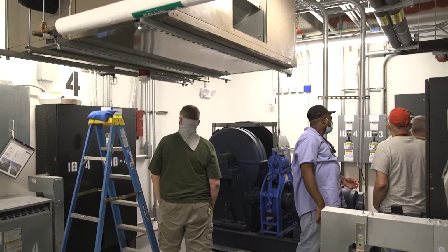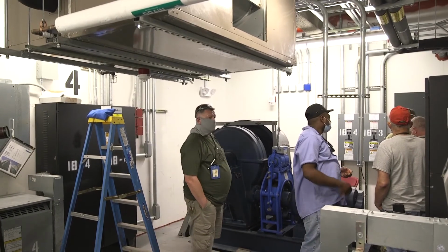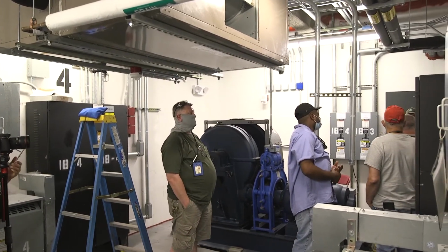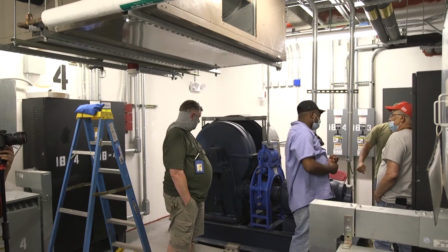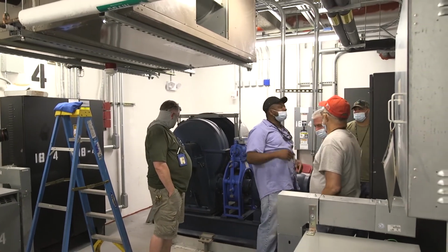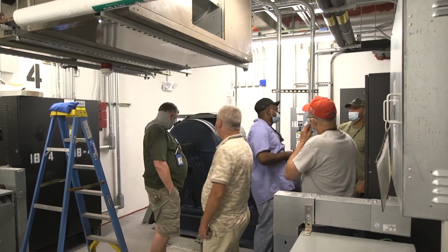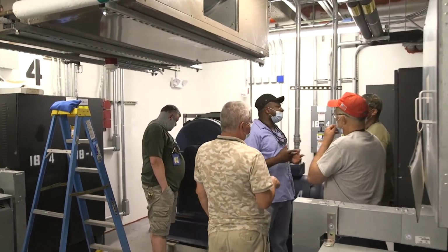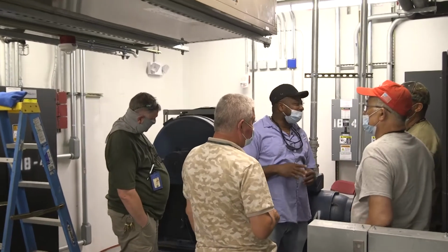So we have to mark that down, that the condenser will keep on running. Well, the way they wired it, or the field wired it, if they shut this down, the condenser continues to run, and then this is going to freeze up. Yeah, but it could have been wired differently, but I'm not going to get into that.